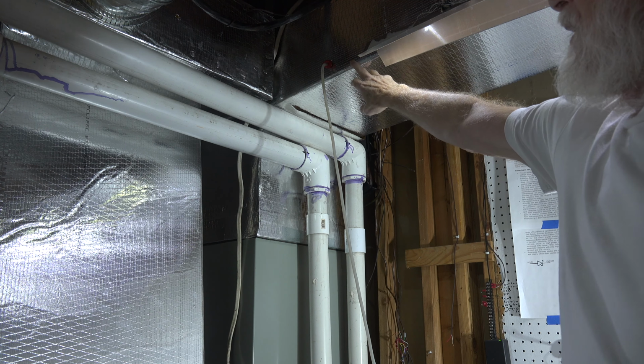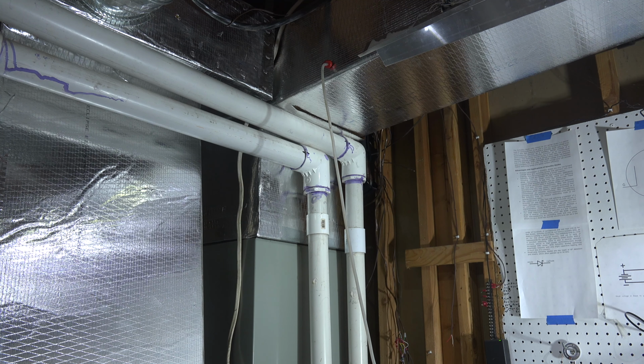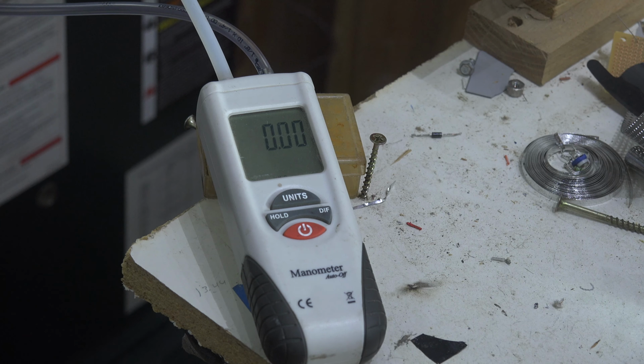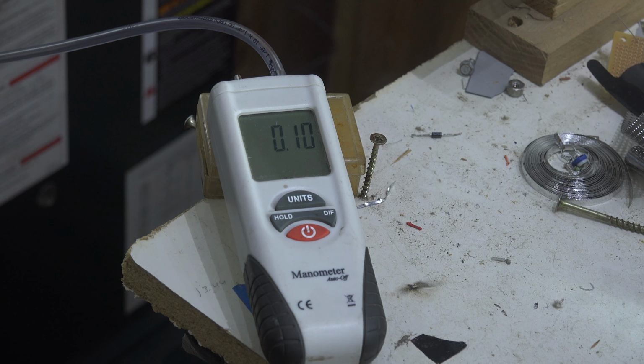Now here I'm set up on the other trunk line, and we're looking at the pressure in that other supply. And remember, we didn't have a whole lot to start with, so let's see what drop there is across that T for this other trunk line. Okay, looking at the pressure drop across the T on this side, it's pretty much 0. Now remember, there's only like 1/10 of an inch water column total pressure in this entire duct system. So it's not very big, so there's not a whole lot of loss in this. This is not where our problem lies.